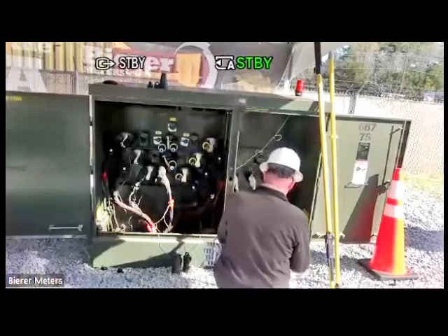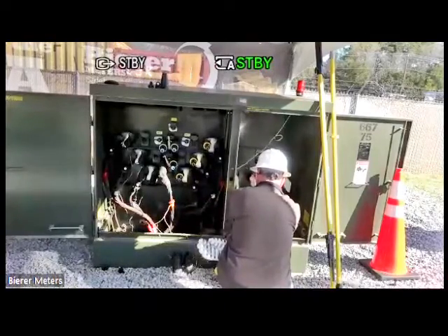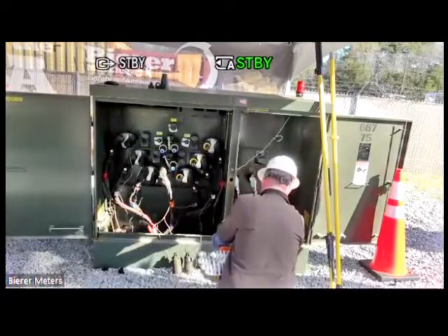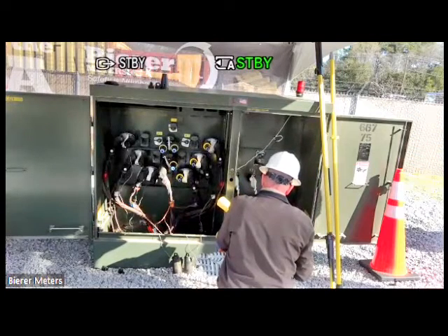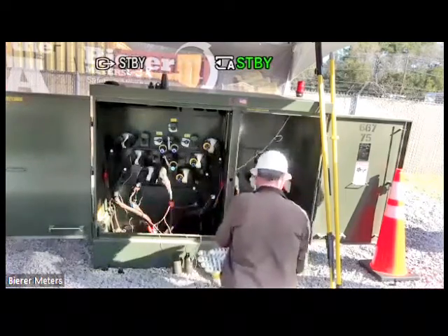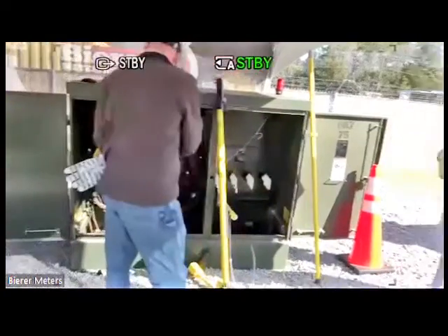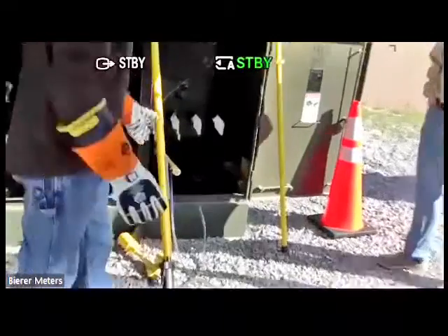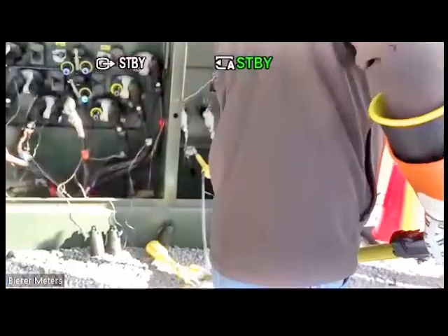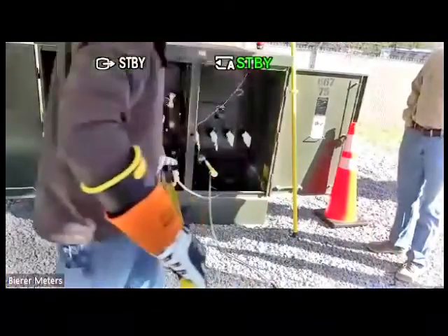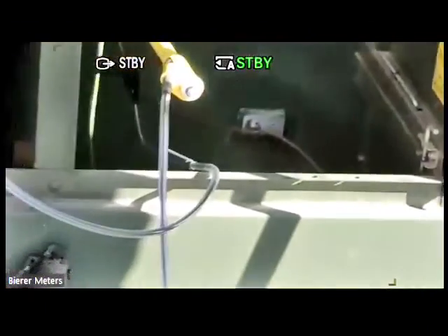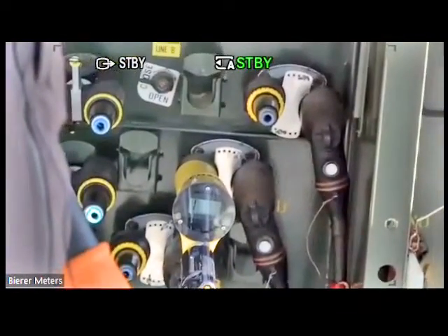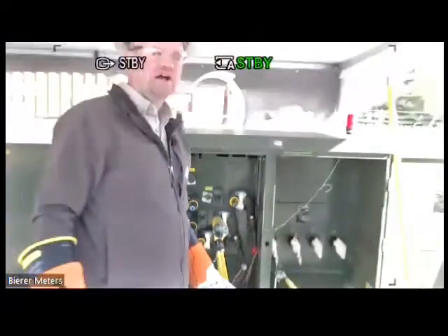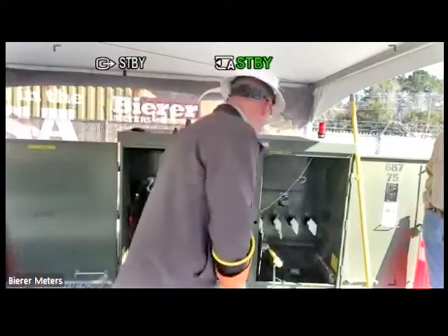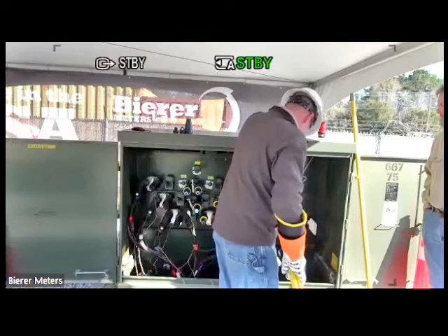And a highline resistive voltmeter. So again, it's just an alligator clamp connected to the ground. I want to attach this meter probe to one of the primary bushings and see what my potential is. So again, highline resistive voltmeter. Some utilities use this with a 100-foot cable, 50-foot cable. Very rarely, if ever, are they going to use a short cable like what I'm about to demonstrate here, just because there's really no need to do that. Now I left that on the 20 kV switch position or 2 kV, one of the two. Again, that's my one. Again, just demonstrating it's not going to hurt the tool. It's just giving you a one, telling you it's out of range. Yep, left it in 2 kV.